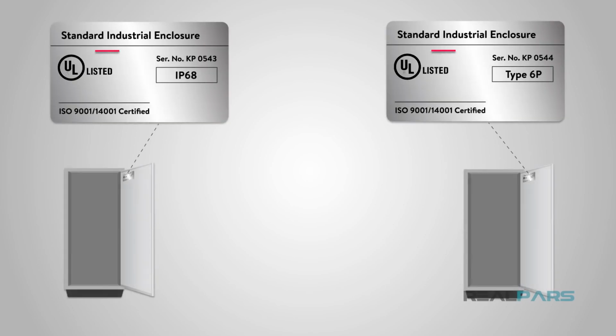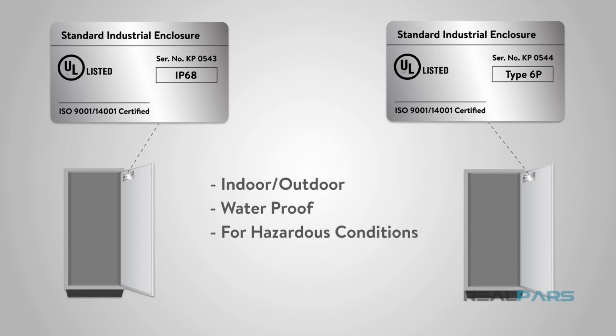Each enclosure will have an electrical safety rating designated by UL, the Underwriters Laboratories, who govern electrical safety. They will also have an IP rating, or NEMA classification, which designates the enclosure to be indoor or outdoor, waterproof or water-resistant, suitable for hazardous conditions, dustproof, or explosion-proof.